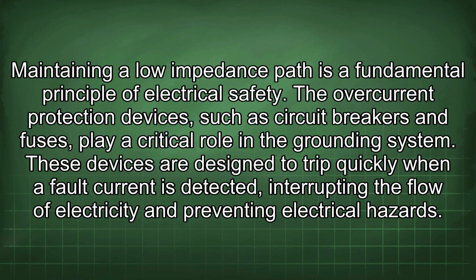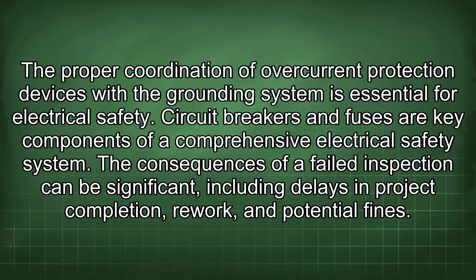The overcurrent protection devices, such as circuit breakers and fuses, play a critical role in the grounding system. These devices are designed to trip quickly when a fault current is detected, interrupting the flow of electricity and preventing electrical hazards. The proper coordination of overcurrent protection devices with the grounding system is essential for electrical safety. Circuit breakers and fuses are key components of a comprehensive electrical safety system.